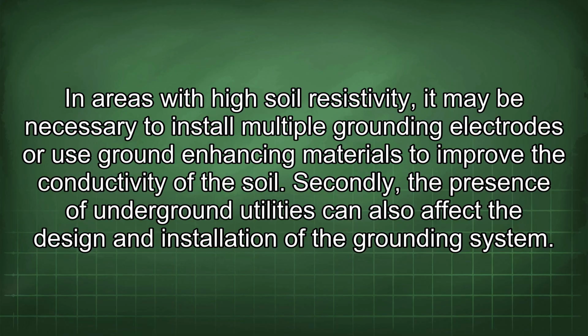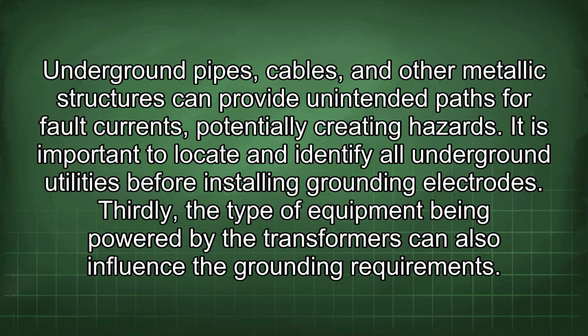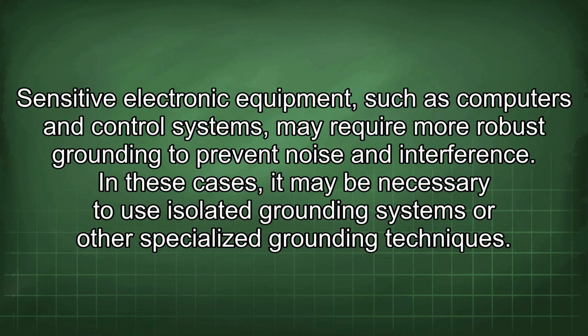Secondly, the presence of underground utilities can also affect the design and installation of the grounding system. Underground pipes, cables, and other metallic structures can provide unintended paths for fault currents, potentially creating hazards. It is important to locate and identify all underground utilities before installing grounding electrodes. Thirdly, the type of equipment being powered by the transformers can also influence the grounding requirements. Sensitive electronic equipment, such as computers and control systems, may require more robust grounding to prevent noise and interference. In these cases, it may be necessary to use isolated grounding systems or other specialized grounding techniques.